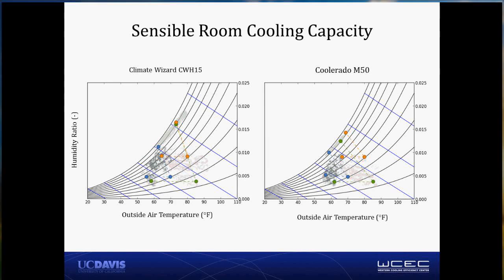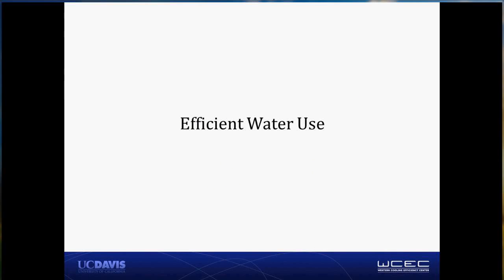I won't go into much detail here, but we've resolved the performance of these systems to a very good level of detail. Along with those wet bulb effectiveness charts, you can see from psychrometric results that the supply air temperature from the Climate Wizard is typically somewhat lower than the Coolerado, even though the total cooling capacity and efficiency are very similar.